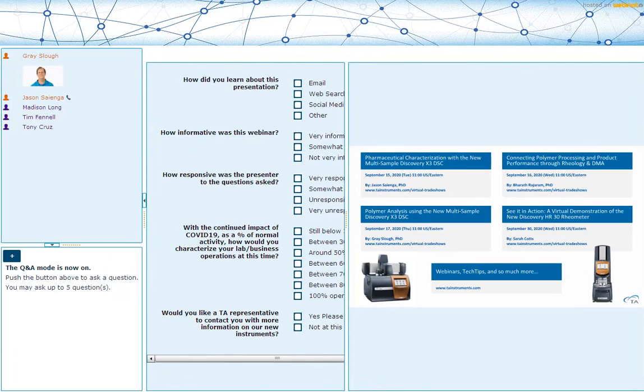You also have the opportunity to seal the old style hermetic pans with the white die sets and the old style crimped pans with the green die set, as well as high volume pans and TGA sealed pans. So the press is designed to accommodate all the pans that we sell for the DSC, minus maybe the high pressure pans, which require a whole different setup. Hope that answers your question. Okay, thank you.